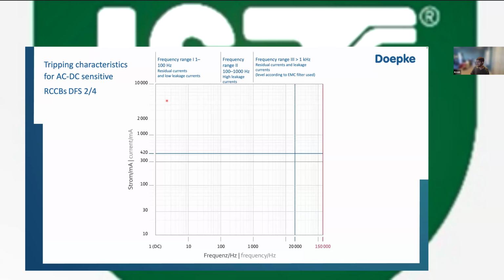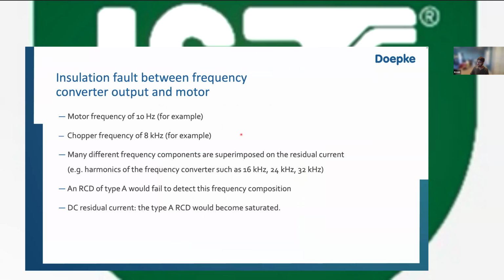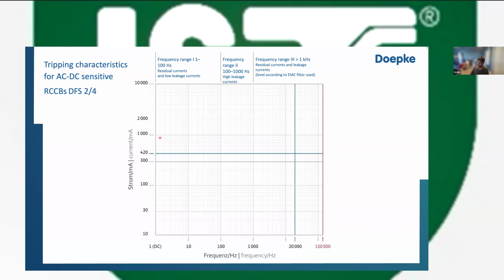If we talk about this particular manufacturer, Doepke, which is what I'm going to talk about, generally I've kept this plan neutral, but just for an example, something that you need to verify is whether your device can actually operate for this entire band of frequencies, up to say 8 kilohertz as an example.